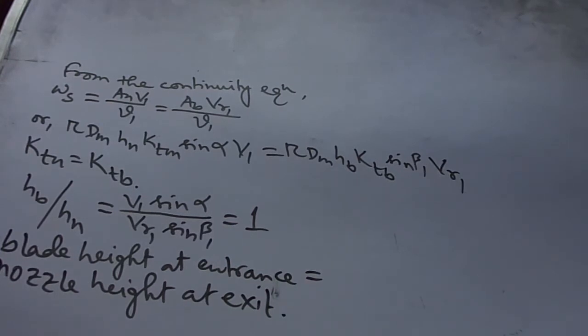It is customary to increase the blade entrance height slightly. This is done in order to avoid spilling of the fluid issuing from the nozzles. This increase in the blade entrance height is called overlap, and is given equally at the root and tip of the blade. This HB exceeds HN by 1.6 mm in high pressure.